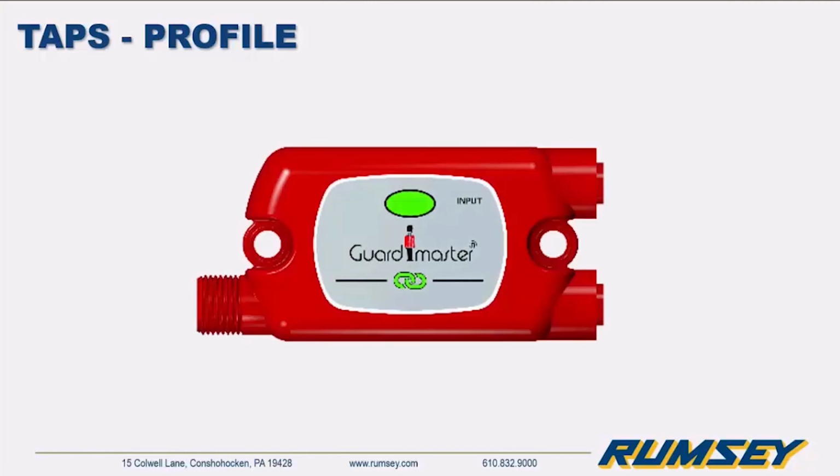Now we're going to get into the specifics of some of the hardware, and first and foremost, that starts with the taps. The taps, from a marketing perspective, are the face of a GuardLink system. If you were able to attend Automation Fair in 2018, you probably saw these. There were quite a few demos that had these on them. They are essentially a mini safety relay that takes a status from an input device, shows its status locally on a machine with a green LED, and then is connected to the next tap with just a standard M12 cable. These are rated IP67, so they can be used in washdown areas.